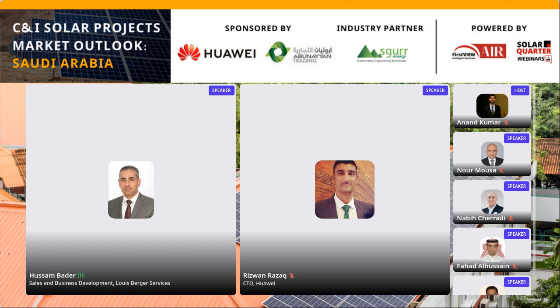Second point related to distortion and harmonics. Yes, we know that Huawei has made great development on their inverters by adding internal harmonics filters. But still we can see distortion or interruption coming from the environment, like clouds, or a sudden interruption from either dust or clouds. This will sometimes make distortion or interruption in the generated energy.